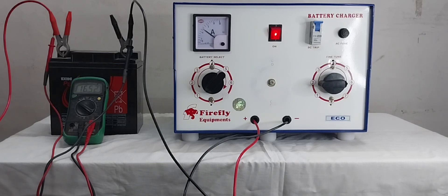Battery gravity must be even in all cells. 1200 and above is recommended gravity. We can check by gravity hydrometer.